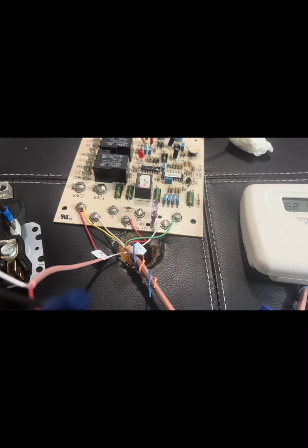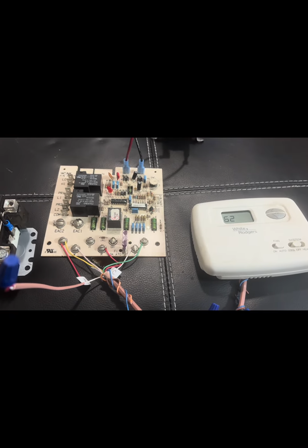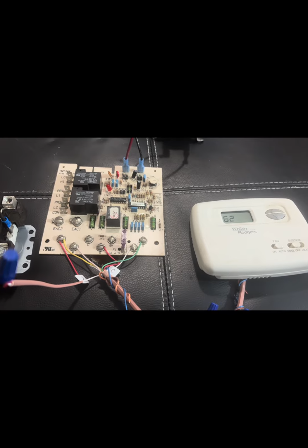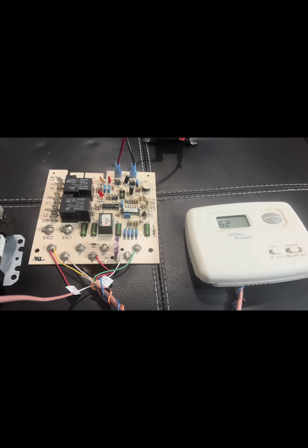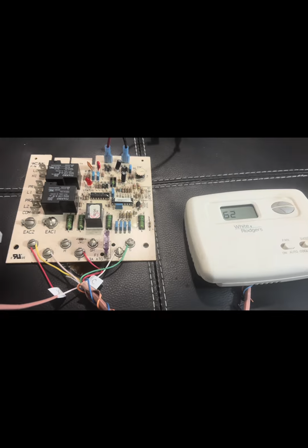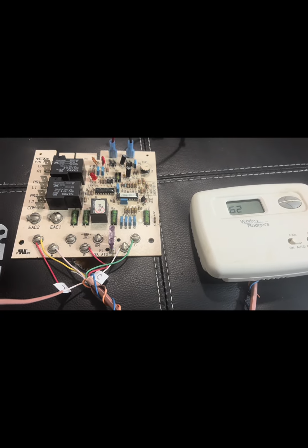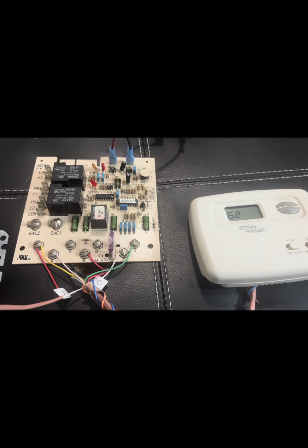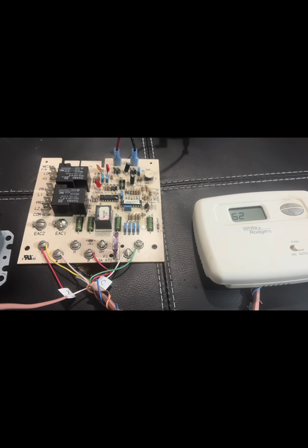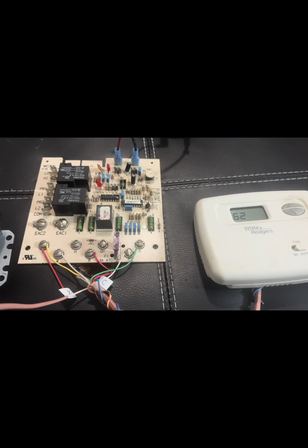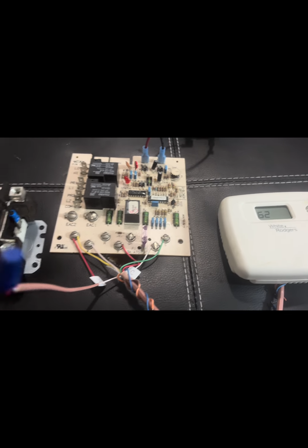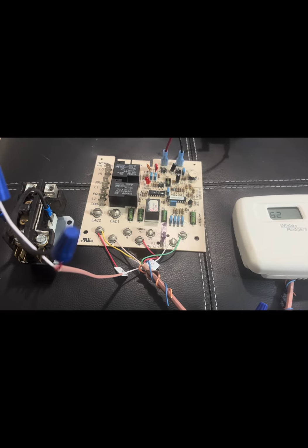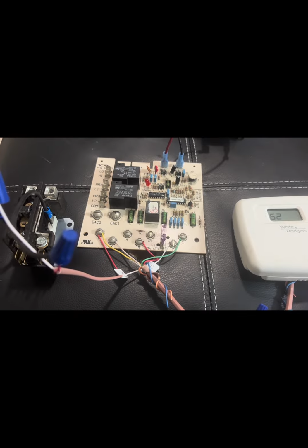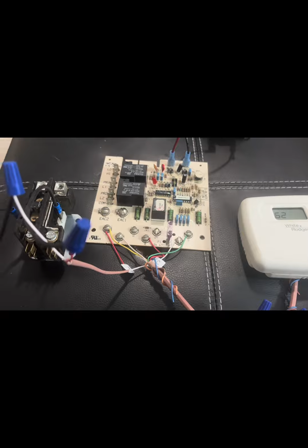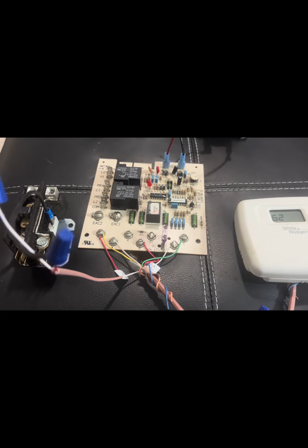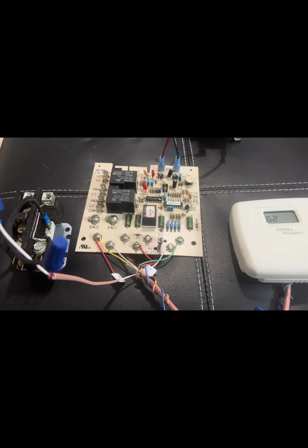Why do straight cool systems only need 2 wires for the condenser? Because it only has one function. A straight cool condenser only needs one function, and that's to cool the house. It doesn't reverse mode, it doesn't heat, it doesn't control backup heat, and it doesn't stage compressors. So all it needs is Y, which equals turn on for cooling, and C to return power path. Straight cool is straight and simple. One more time. A straight cool condenser only cools, so it only needs 2 wires, on for Y and common for C. Y tells it to turn on, C completes that circuit.